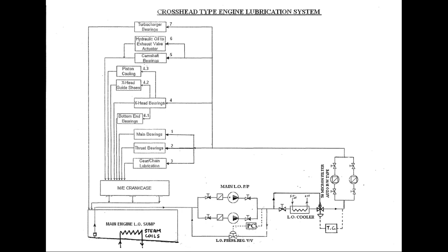Lube oil is also led to the cams, roller guide, camshaft bearings, and finally to the hydraulic pump for actuating hydraulically operated exhaust valves — hydraulic opening, spring-air closing. The rocker arm is absent in large two-stroke engines. From the hydraulic pump, oil is sent for the opening of each exhaust valve.